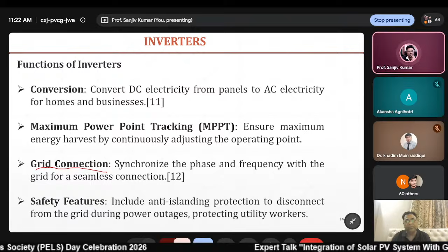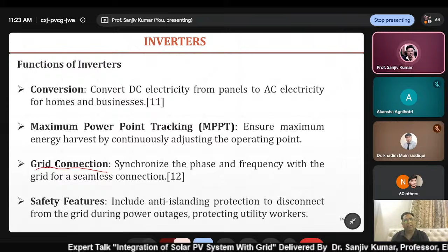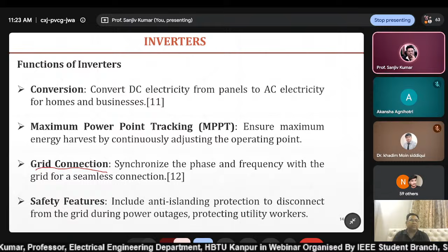When you synchronize with the grid, three components must be ensured: phase sequence, synchronization of phase, frequency, and voltage rating. Your solar panel supplying the grid must have the same voltage sequence, same phase sequence, same voltage level, and the same frequency. Then you can synchronize with the grid.